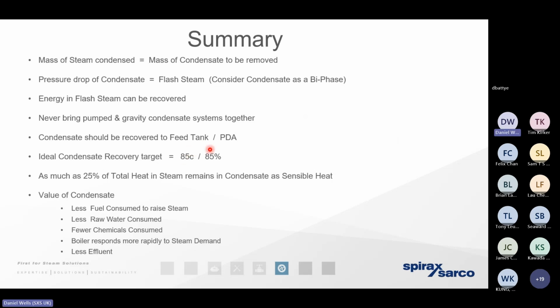If either of those figures are significantly lower, then there's money on the table in terms of efficiency improvements. Please do bear in mind that condensate is only a single phase fluid when it's at a stable pressure. Whenever we've got a pressure drop, we are going to get that expansion. If that expansion is left unchecked, it's a significant inefficiency.